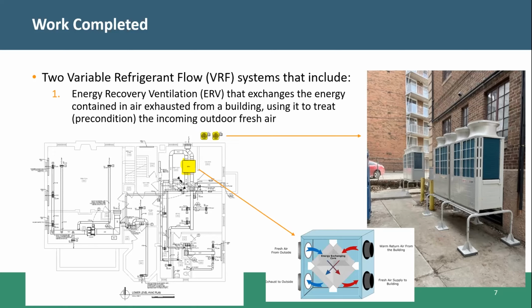Some of the indoor units are ducted, like ones that serve the common areas. The units in the residential rooms are ductless mini split systems, and we'll see those in a picture a little bit later. Air is continuously exhausted from the bathrooms, and it passes through a heat exchanger to precondition the incoming makeup air. The material in the heat exchanger lets moisture pass through, so it not only cools the outside air in the summer, but also dehumidifies it.